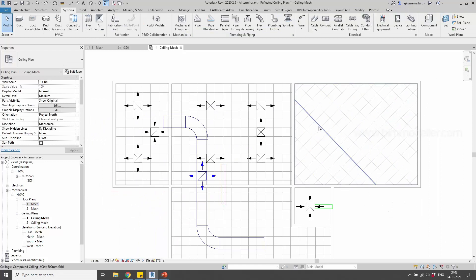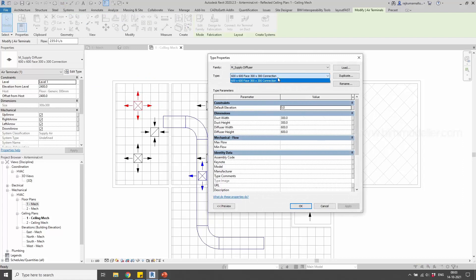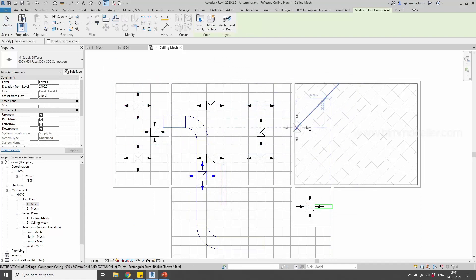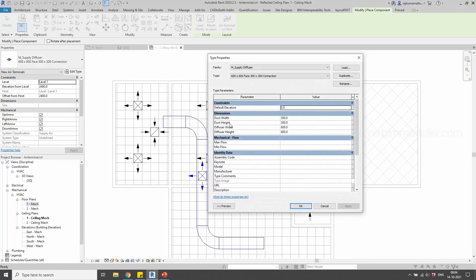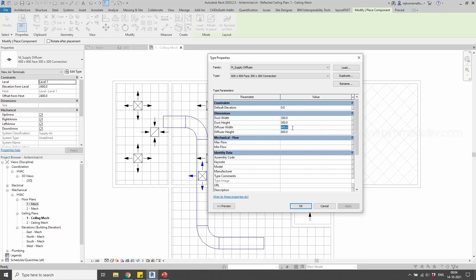To place an air terminal in this room, we need a 600 by 900 diffuser, but by default we only have a 600 by 600 diffuser. To create a 600 by 900, go to Edit Type — only 600 by 600 is available. If I press Create Similar (CS), and go nearby and try to match it, it doesn't match. Using Edit Type, it is a type property of the air terminal. If I duplicate it with the required name — 600 by 900 — and try to change the value to 900, the other value changes automatically. This is because the family has a formula applied where both width and height are always equal.